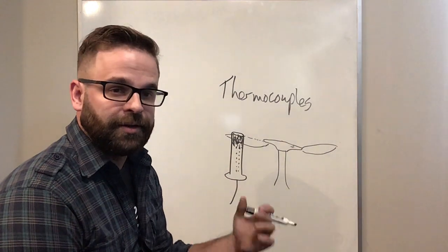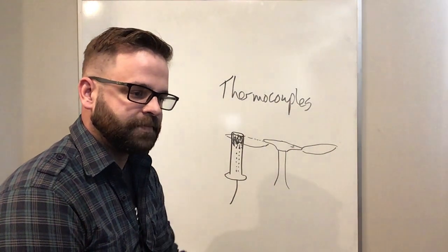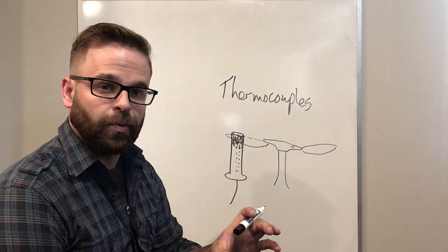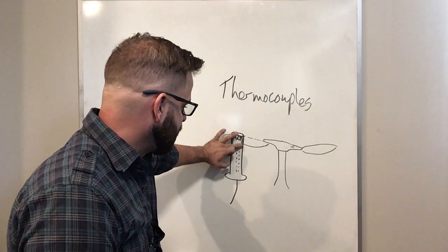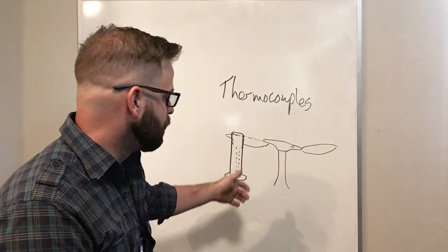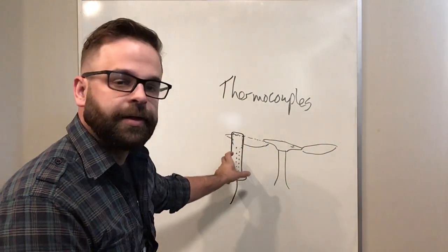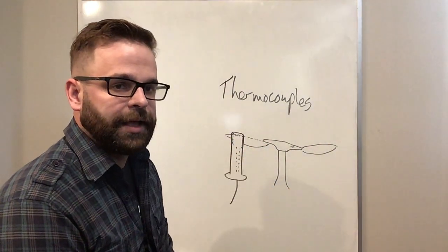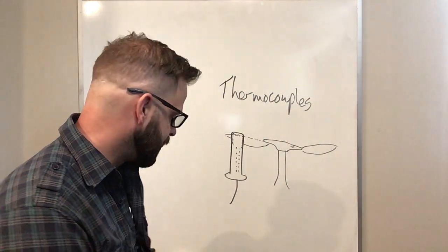So what I've done is I'll go and get a new little scrub brush, like steel wool, and I will clean off the soot with the steel wool, and then it allows the heat to conduct through to that thermocouple again, and produce a voltage to keep that gas valve open and running.